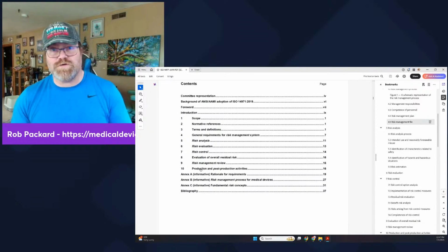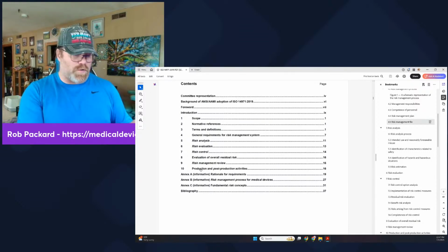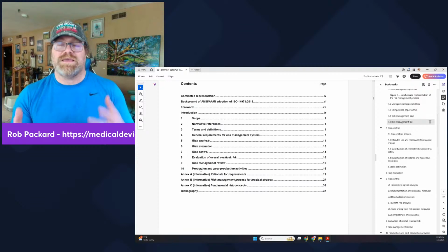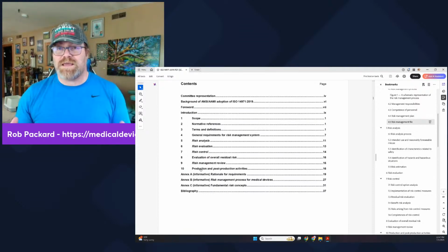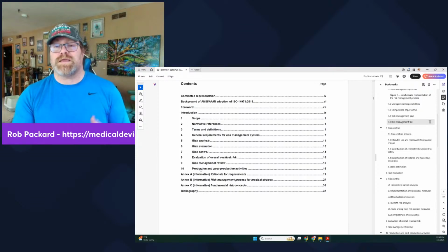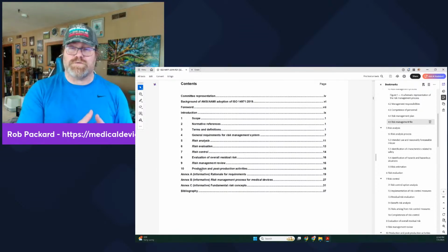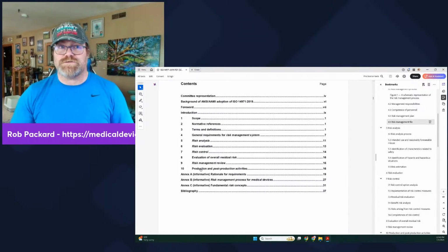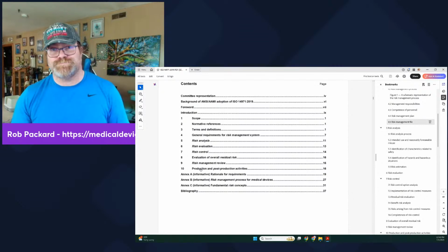If that isn't something you've done before, if you just had one person go off and type a bunch of answers to the 37 questions, that's not hazard identification. You've done a very poor job of identifying hazards. Yes, you have identified some by answering those 37 questions, but it's a team effort, cross-functional, and it's supposed to be done multiple ways, and it's supposed to be planned because you had a risk management plan, said you would do that, and you document it, and now we have a list of hazards. And you're going to update that over time as you identify new hazards.